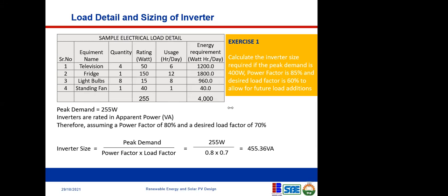Okay, 784. Good. Thank you. I gave an approximate value, although it's 784.31. Now you size the battery. So that will be 4 batteries, 200 ampere. Sorry to preempt you, Chima. Okay, no worries, we'll get to that. Let me proceed. I just want us to keep trying this so that if there's any confusion, it can be clarified. Now let's move ahead.